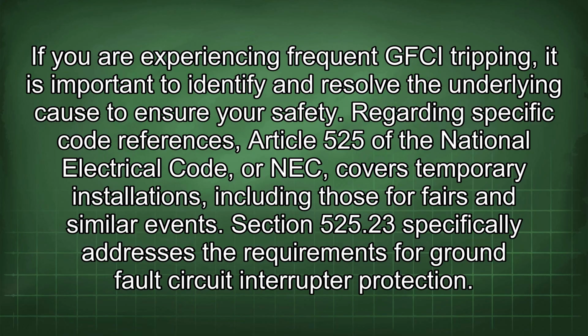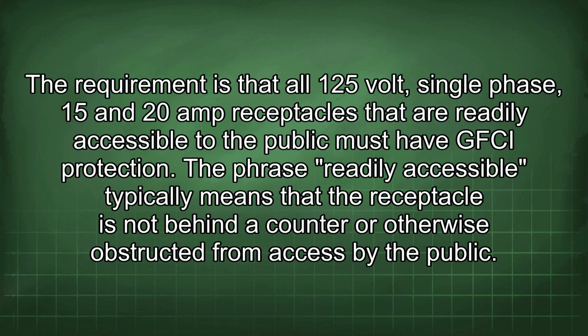Regarding specific code references, Article 525 of the National Electrical Code, or NEC, covers temporary installations, including those for fairs and similar events. Section 525.23 specifically addresses the requirements for ground fault circuit interrupter protection. The requirement is that all 125-volt single-phase 15 and 20 amp receptacles that are readily accessible to the public must have GFCI protection. The phrase readily accessible typically means that the receptacle is not behind a counter or otherwise obstructed from access by the public.